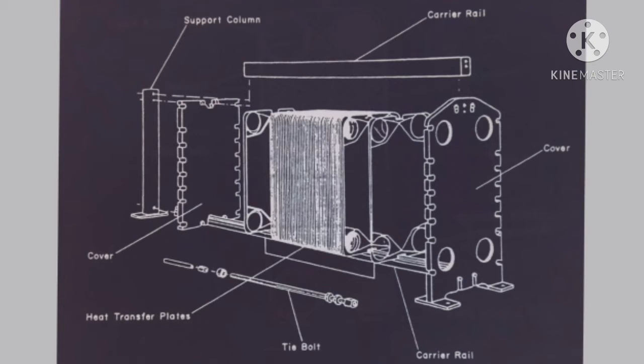The next disadvantage is bonding material between plates limits the operating temperatures of the cooler. The biggest disadvantage is that pressure drop caused by the plate cooler is higher than in shell and tube type heat exchangers. Pressure drop is more in plate type heat exchangers compared to shell and tube type heat exchangers.